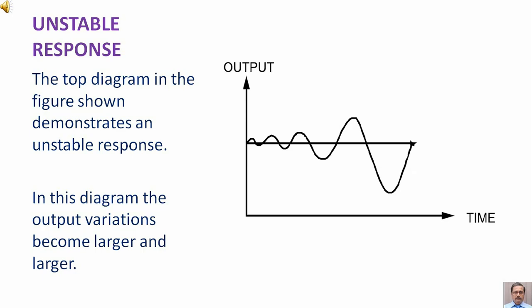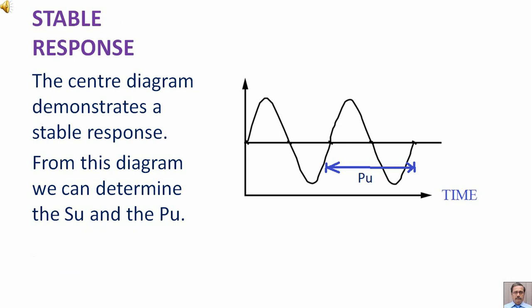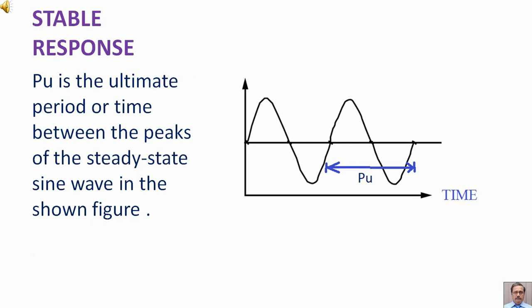The center diagram demonstrates a stable response. From this diagram, we can determine the S subscript U and the P subscript U. The P subscript U is the ultimate period or time between the peaks of the steady-state sine wave in the shown figure.